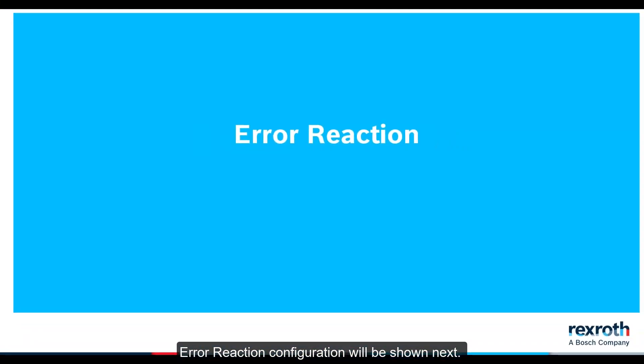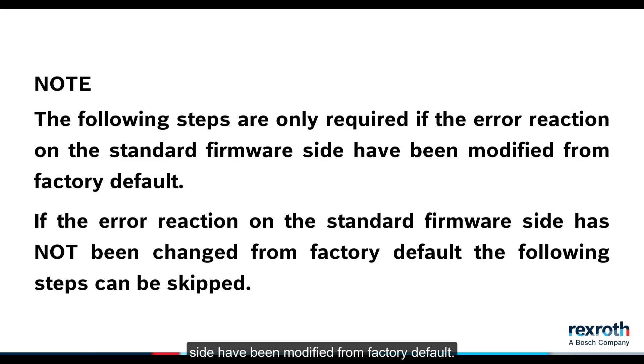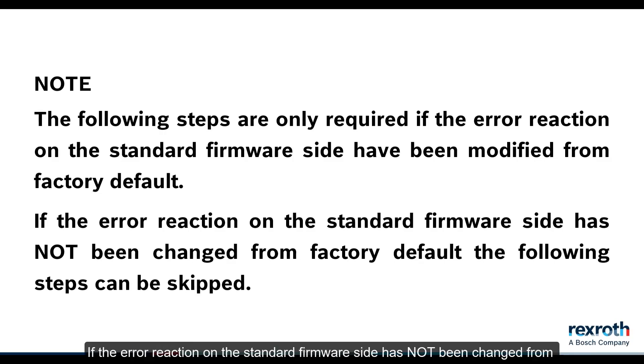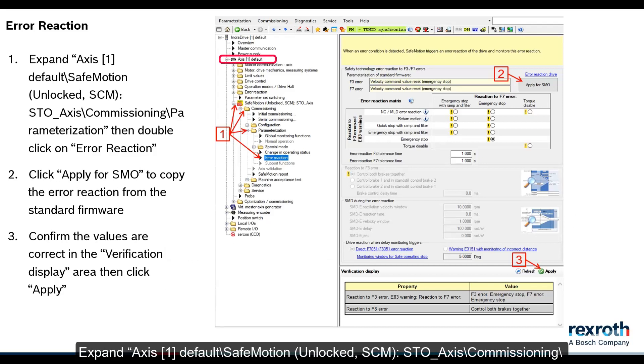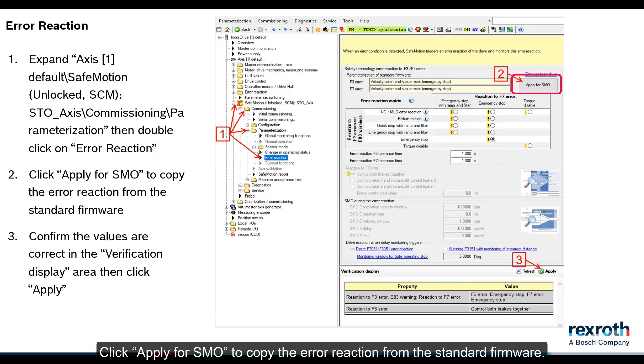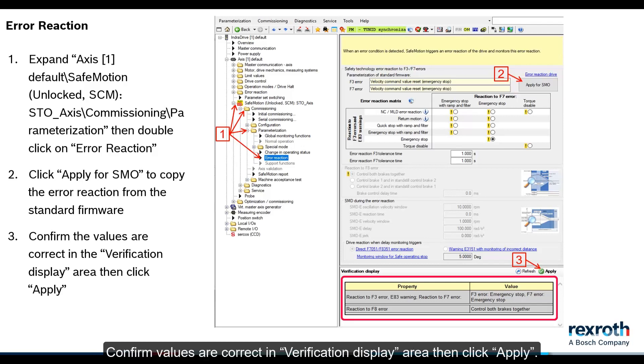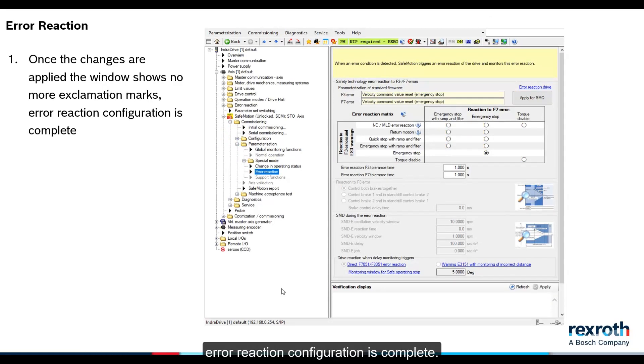Error Reaction Configuration will be shown next. The following steps are only required if the error reaction on the standard firmware side has been modified from factory default. If the error reaction on the standard firmware side has not been changed from factory default, the following steps can be skipped. Expand Axis 1 Default, Safe Motion, Unlocked, SCM, STO Axis, Commissioning, Parameterization. Then double-click Error Reaction. Click Apply for SMO to copy the error reaction from the standard firmware. Confirm values are correct in the Verification Display Area, then click Apply. Once the changes are applied, the window shows no more exclamation marks. Error Reaction Configuration is complete.